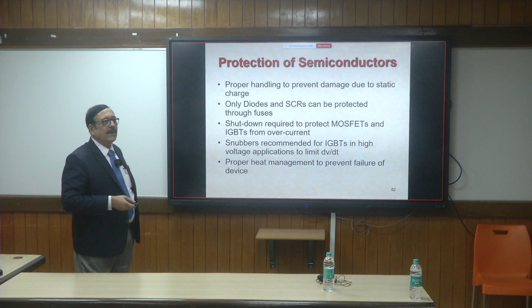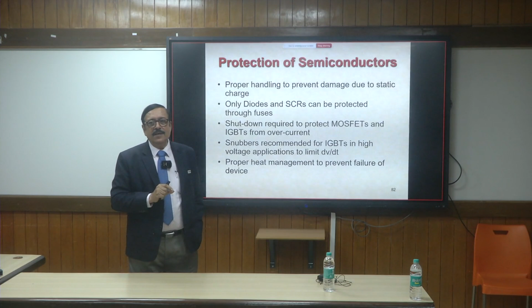Only diodes and SCRs can be protected by a fuse, because you can define an I-squared-T rating, basically a power rating for the device, since their voltage drop is more or less constant. You can't do that for a controlled device, because the voltage drop depends upon the drive you are putting in. So you don't have a fixed I-squared-T for that device, making it not possible to coordinate a fuse with them. You can coordinate a fuse with the bonding wires inside, but not with the devices.